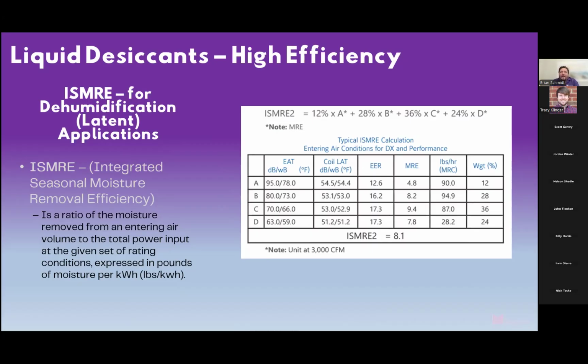Now, not every manufacturer of HVAC equipment has to have an ISMRE2 value. However, for manufacturers that are primarily or solely 100% outside air machines, they do have to provide an ISMRE2 value. We do have a return air knockout, so we are not 100% only outside air. We do have the capability to have mixed return. However, we are a primarily 100% outside air DOAS machine, and so we do list our ISMRE2 value.